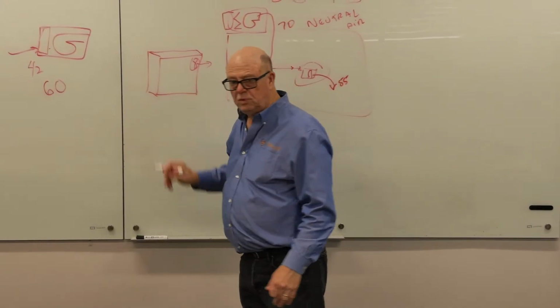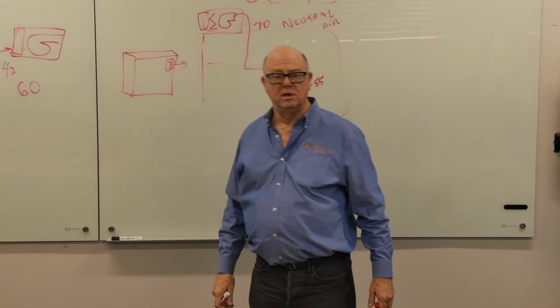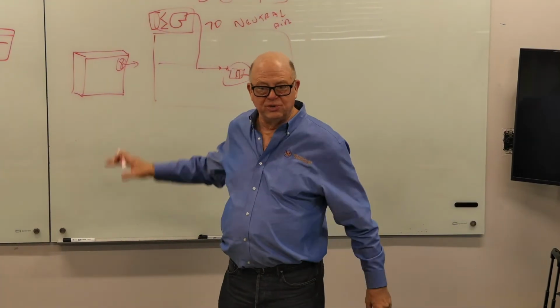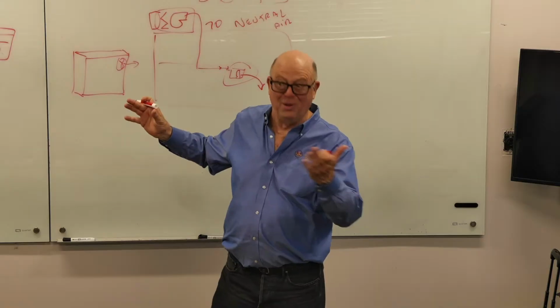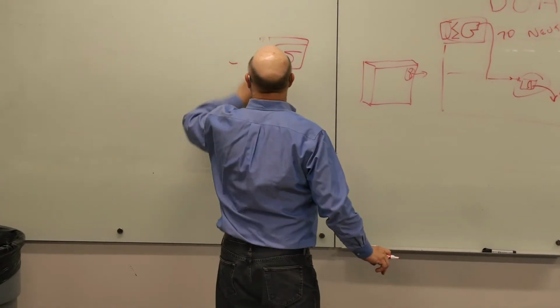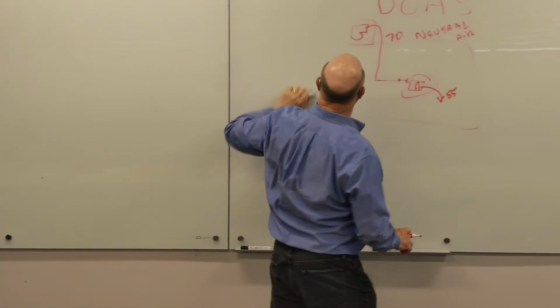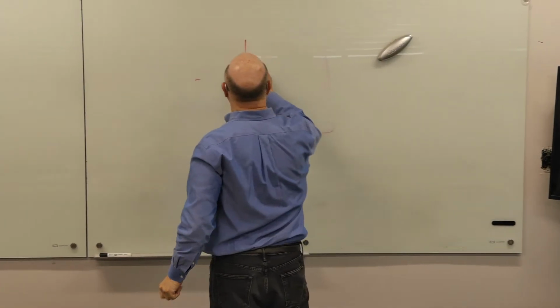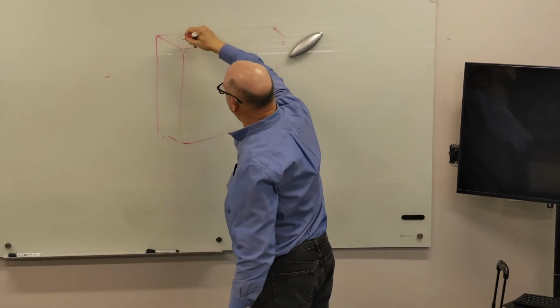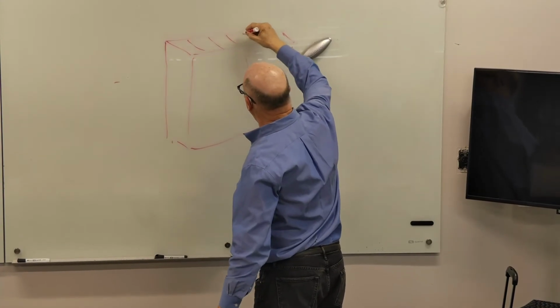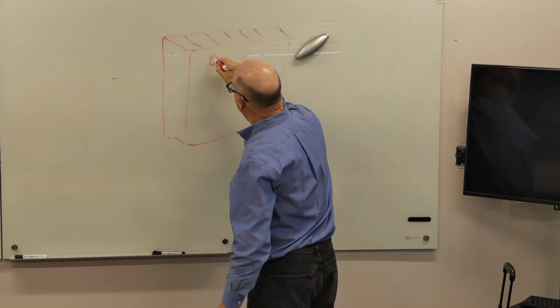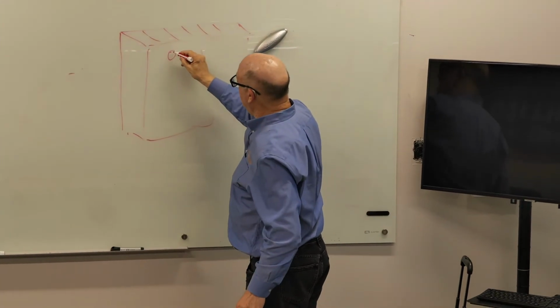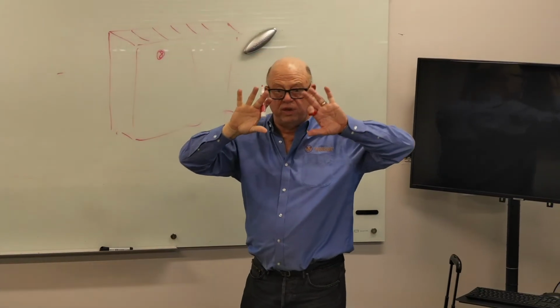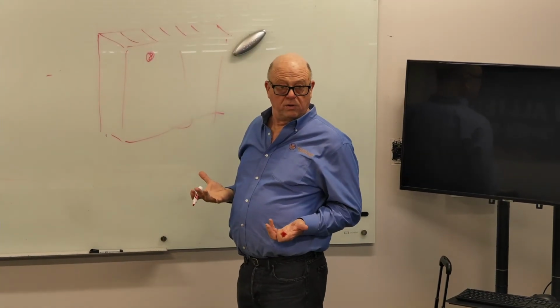When you've got a server rack and you've got a ton of these, do you have them blowing different ways, or do you set them all the same? You should set them all the same. And that is the importance in server room design. What you want to have happen is you want to concentrate the heat in one place. So if this is my server rack, and it goes down here, and it's full of servers, and I'm standing in this aisle, looking at all the little muffin fans, because they're right there, blowing in my face. Am I standing in the hot aisle or the cold aisle?